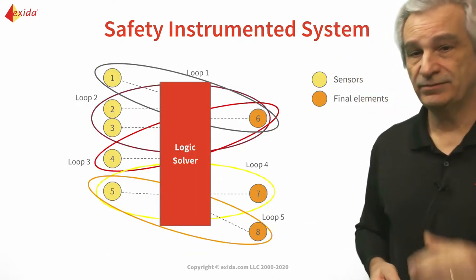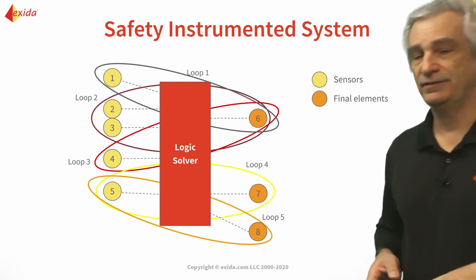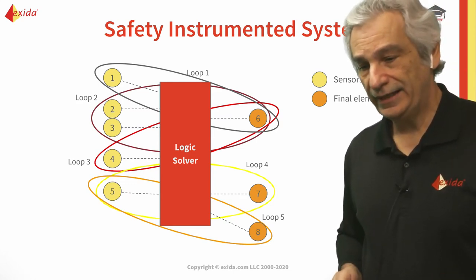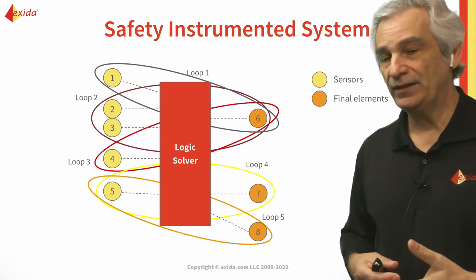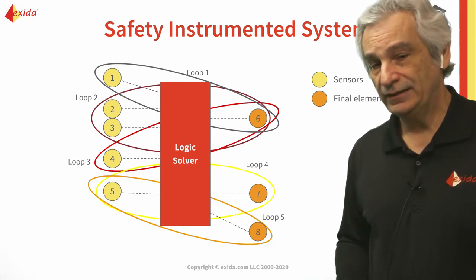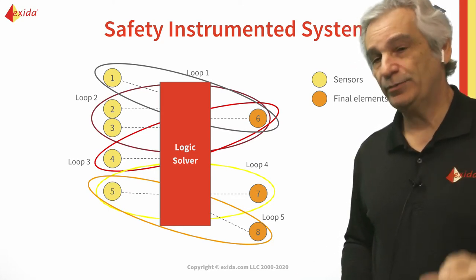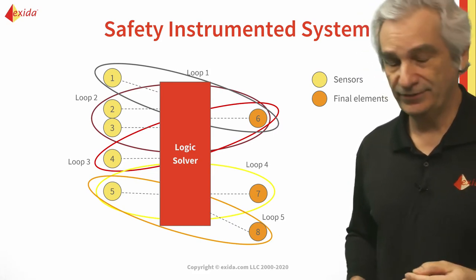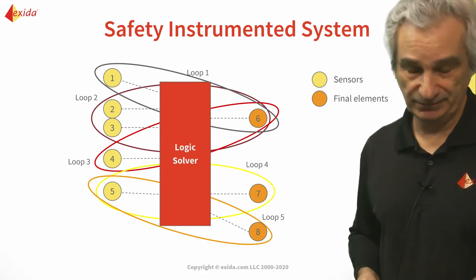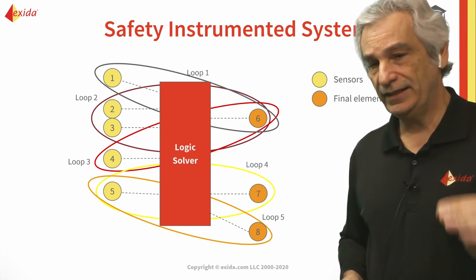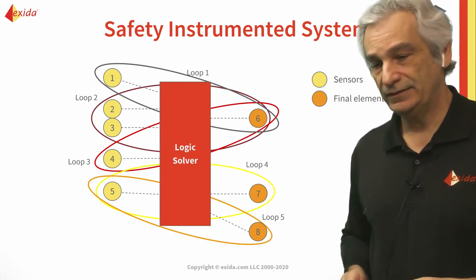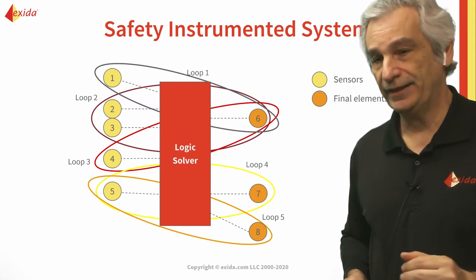When you look at the safety instrumented system, you could have different safety instrumented functions, and each of these is dealing with a single hazard. So you could have a situation with both high pressure and high temperature, but there will be two separate SIFs — one SIF to deal with the high pressure and one SIF to deal with the high temperature. That's the way we design it: a specific, single safety function to automatically bring us back to the safe state.